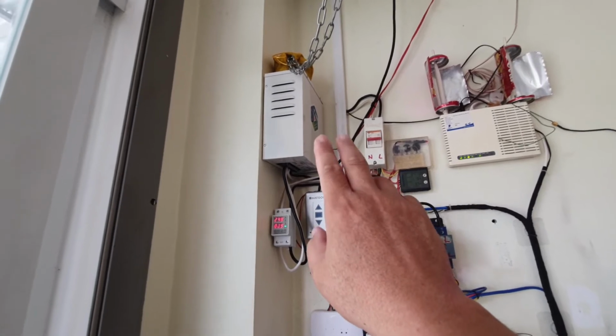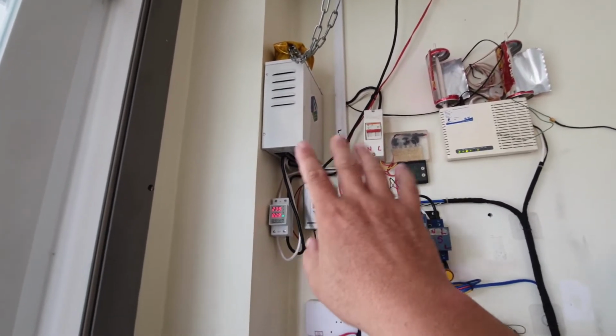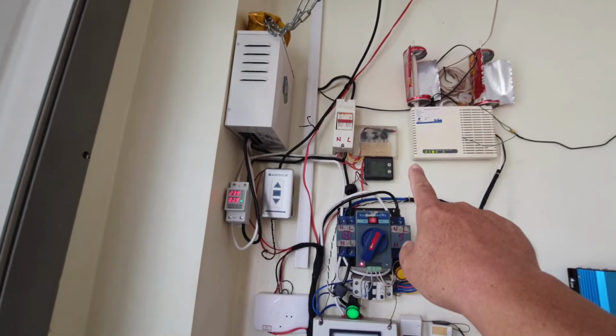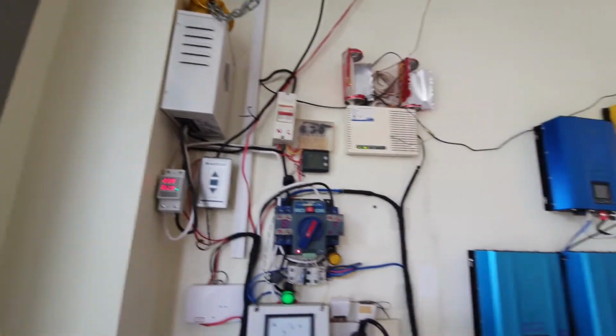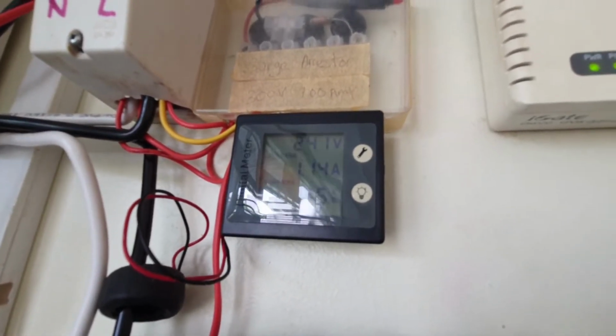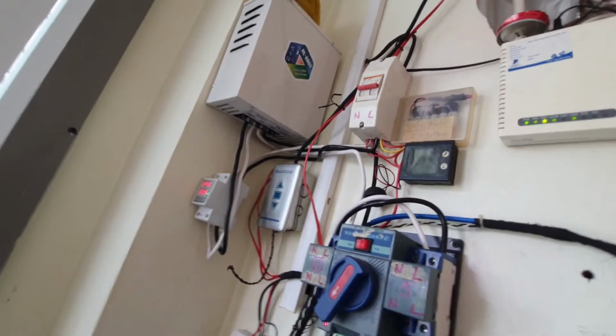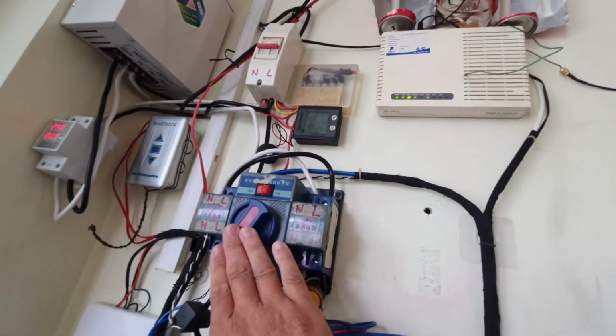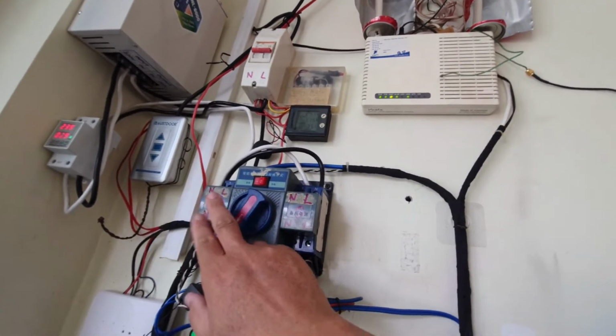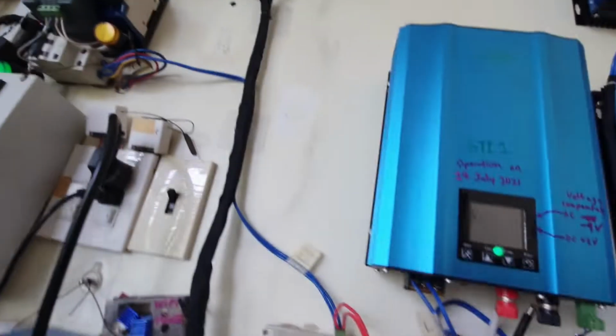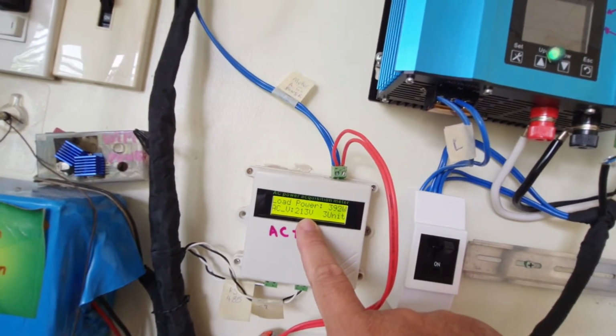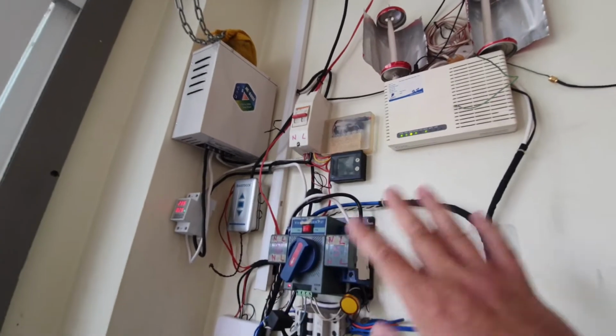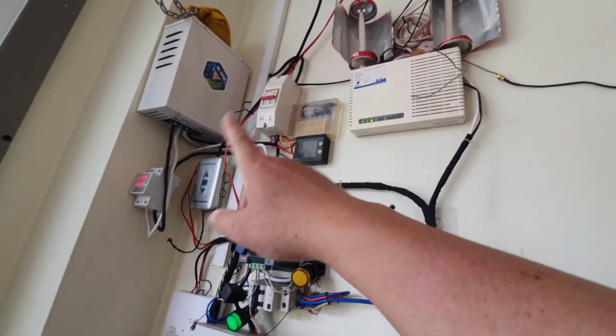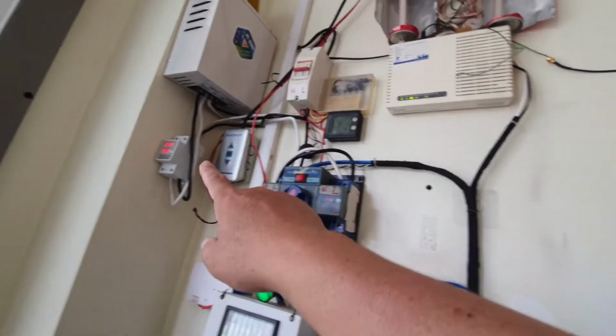This transformer lowers the voltage by about 10%. I'm usually getting 241 now, let me zoom in to show you, 241 here. After the transformer it goes into the ATS, the automatic transfer switch. So now it's 241, but at the meter here I'm getting 213. This is the work of this transformer, it lowers the voltage a bit so I have more spare room for any surge, because the surge might go through this too.